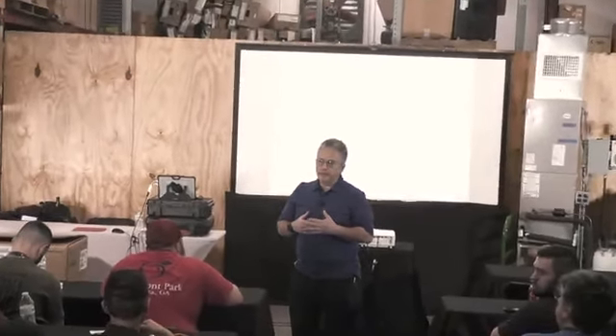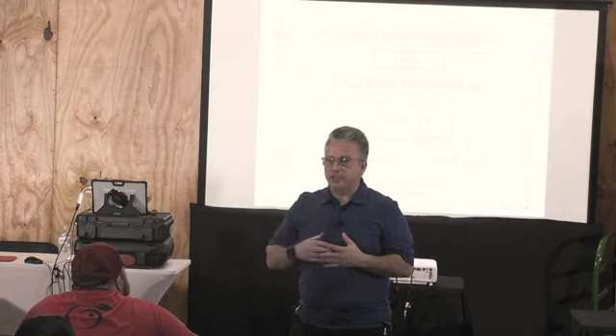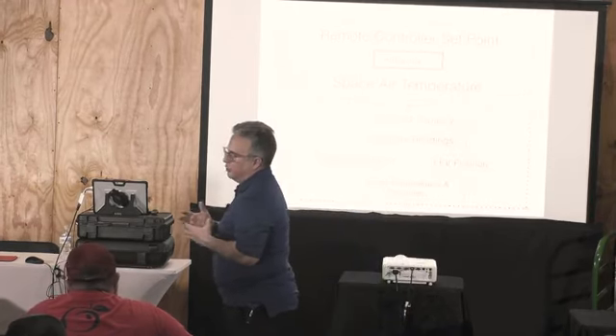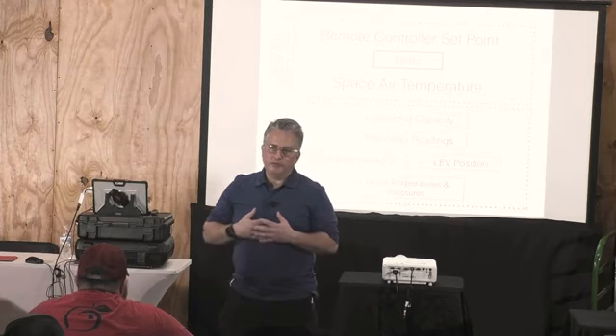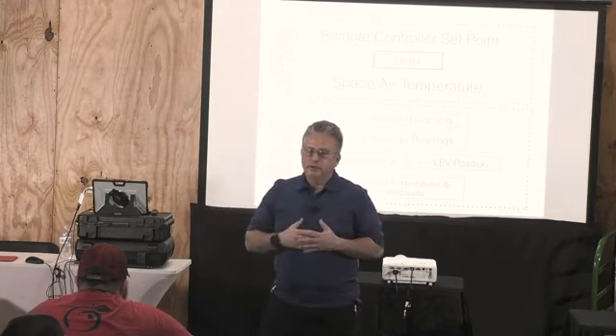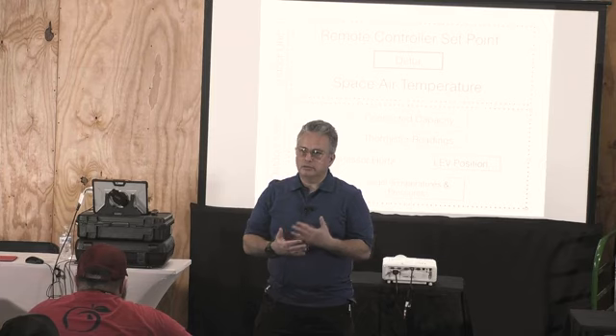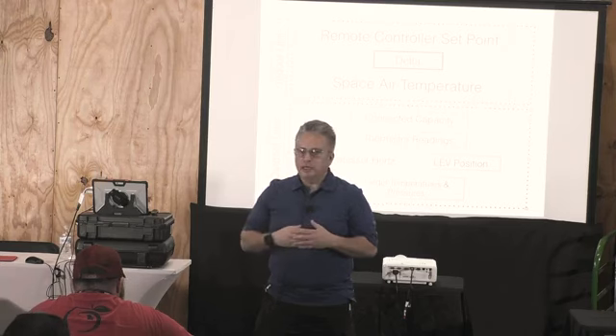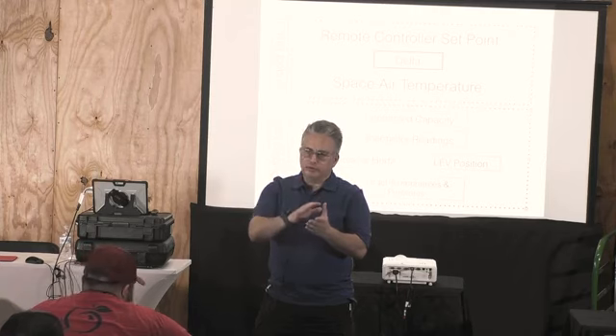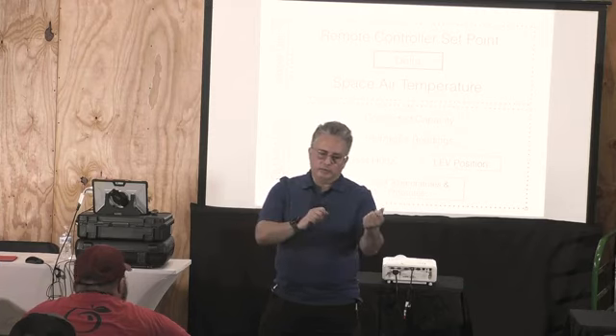Residential? Yeah. So okay, I'm glad you said beach, because the salt content of the air is going to destroy a lot of things, right? So what I would recommend is that they clean the coils once a month with fresh water only, because the coil already has a film on it. And then as far as the controls, you can pot the controls, the PCB. Potting the board means that you're just putting a paste on there, a silicone, and you have to remove it and then pot the back of it, put it in the front, and you can put some in the front too.